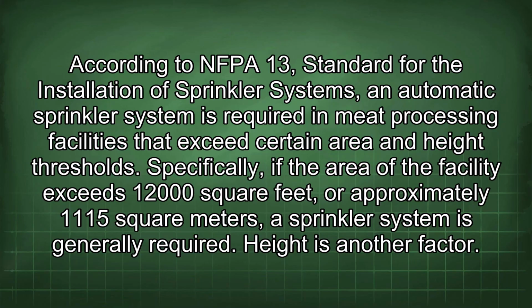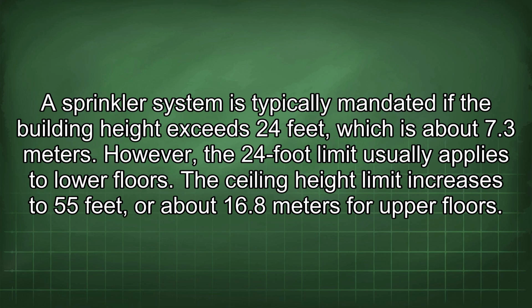According to NFPA 13, standard for the installation of sprinkler systems, an automatic sprinkler system is required in meat processing facilities that exceed certain area and height thresholds. Specifically, if the area of the facility exceeds 12,000 square feet, or approximately 1115 square meters, a sprinkler system is generally required. Height is another factor. A sprinkler system is typically mandated if the building height exceeds 24 feet, which is about 7.3 meters.